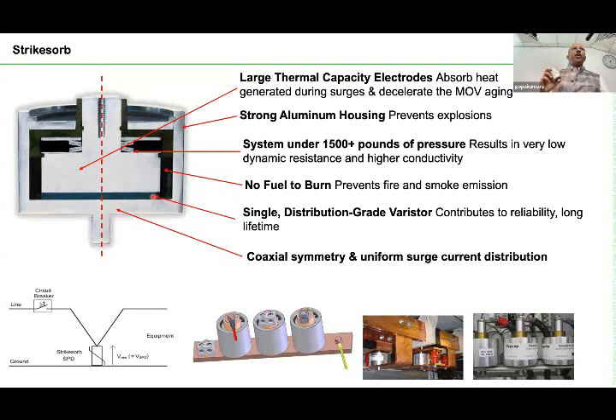As I said, SPDs always fail because of heat. Once the current flows through the SPD, it heats up, and because of the heat, after some time, it fails. So you can increase the quality of the SPD if you remove the heat as quickly as possible. That is what is done here. Very simple. This pressed aluminum acts like a heat sink. So even if the SPD heats up, it won't fail as fast as the other one.